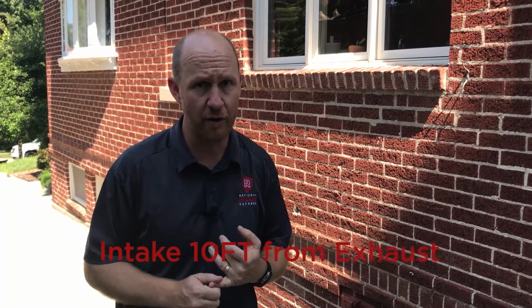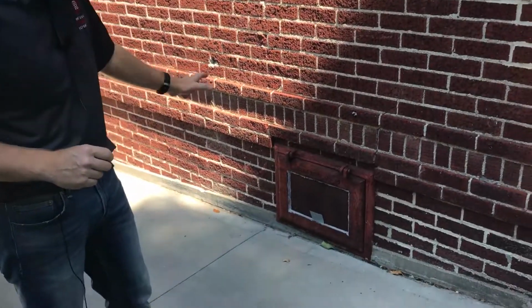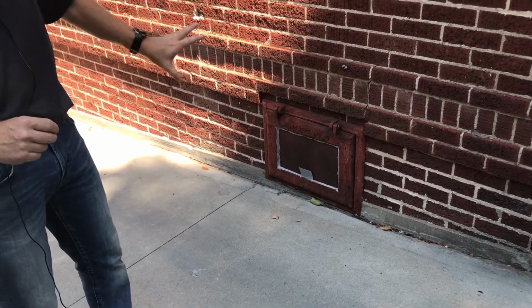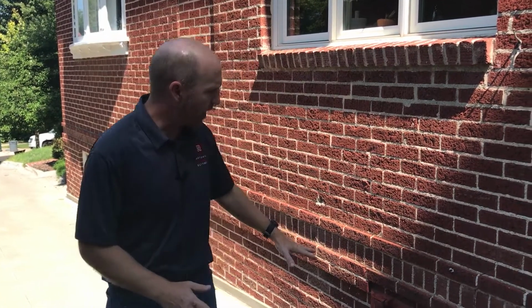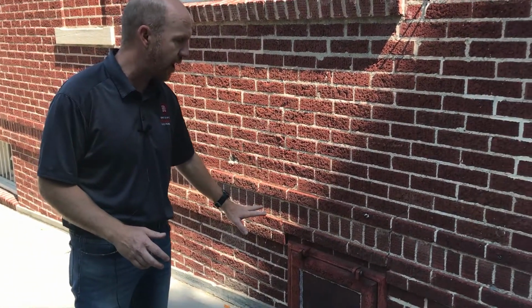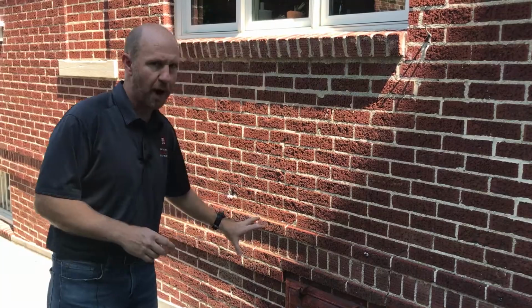You also need to make sure that it's over 10 feet from any exhaust location from the house. So if you have HVAC exhaust or dryer vent exhaust to the outside, your intake air needs to be 10 feet from that, okay? So we found a good location with this home. We're going to use an old coal chute here that is not being used anymore, obviously, and that's what we're going to use for our intake. We feel that's a good location here because it's in a narrow part of the driveway where no car sits and idles, because if you did, the doors wouldn't open. So we know that this is a safe area for fresh air coming in. We'd like it a little bit farther off the ground if we could, but it's okay because snow doesn't build up here. The wind blows it away, and the homeowner shared that with us. So great spot for intake air.